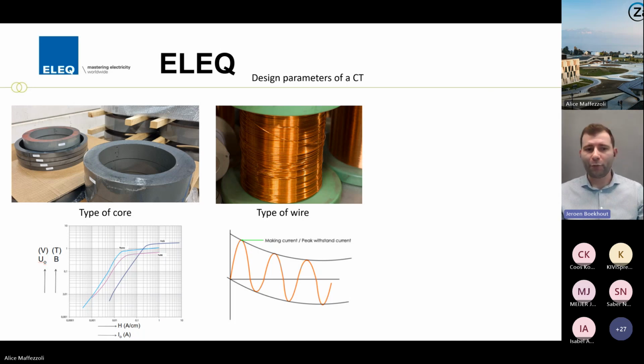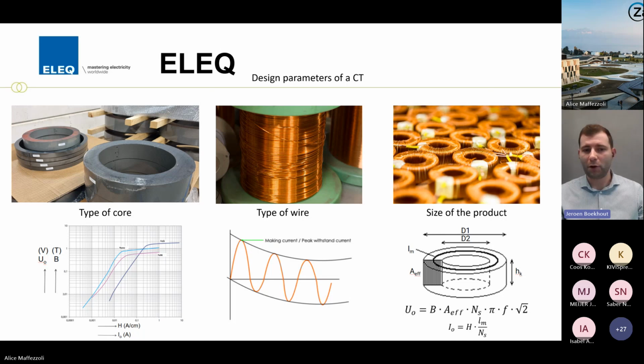And going for multiple wires in parallel is sometimes a way to adjust the ratio error. Because of the iron core losses of the CT, there's a natural ratio error compared to a perfect transformer. By working with parallel wound cables, you have the option to take off one part of, for example, 2 parallel windings, and therefore compensate the error minimally, compared to having one winding and taking one off. So core losses leading to a small error will give us a choice here in wire as well.